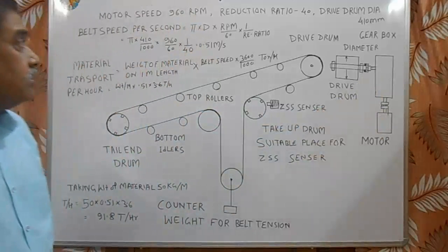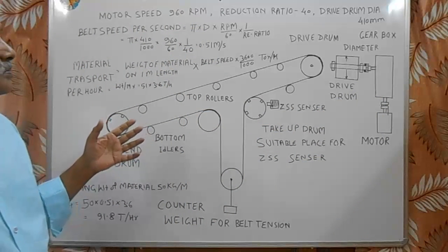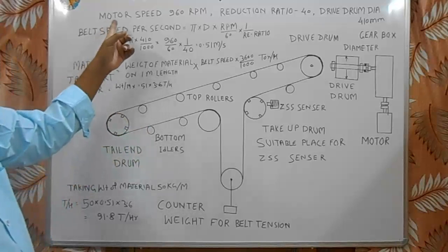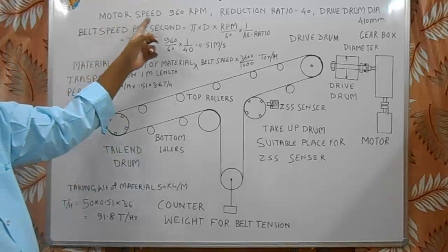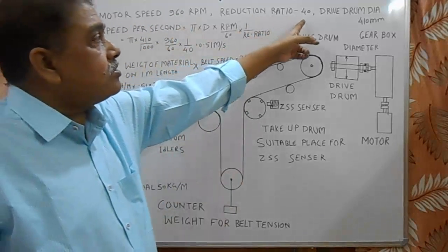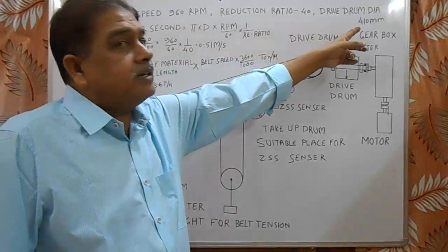For calculation of material handling per ton per hour, we need to have these things. First one motor speed, that is 960 rpm in this case. Reduction ratio of gearbox that is 40, and drive drum diameter here it is 410 millimeters.